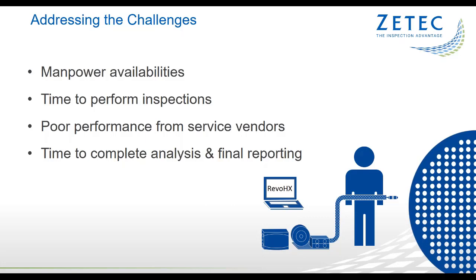In addition, the training required for these resources is more unified and not necessarily independent roles. When it comes to time to perform the inspection, it's another success with the RevoHX-based system. When you hand over the mundane and redundant processes to an automated system, you remove fatigue factors and the associated human errors that result. This eliminates costly retesting of tubes and keeps the inspection rolling at a predictable pace.